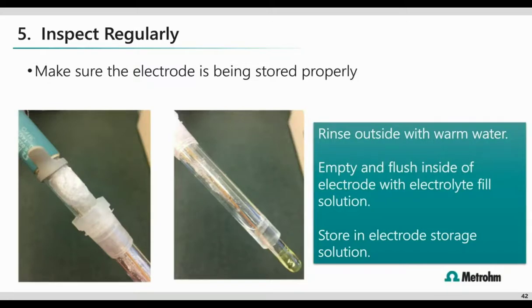Here we see an electrode that has been put away with the fill port plug open and not in the storage solution. What we end up with is an electrode with a reference system that is completely non-functional. You can try to revive it by rinsing the outside with warm water, emptying and flushing the inside of the electrode with the electrolyte fill solution. And remember, do not use water, and store the electrode overnight in the storage solution. After all this, I would still recommend going back and performing a calibration check to verify that it was permanently damaged. Hopefully these tips will help you determine when your electrode needs replacement.